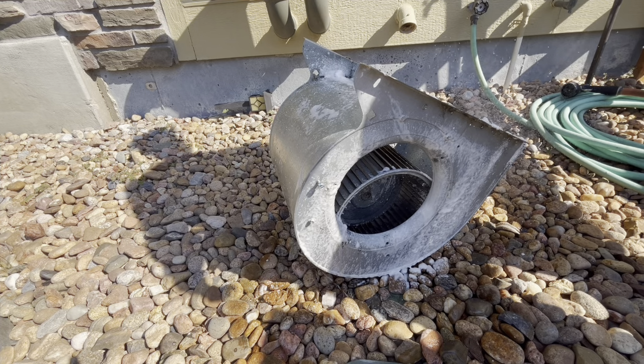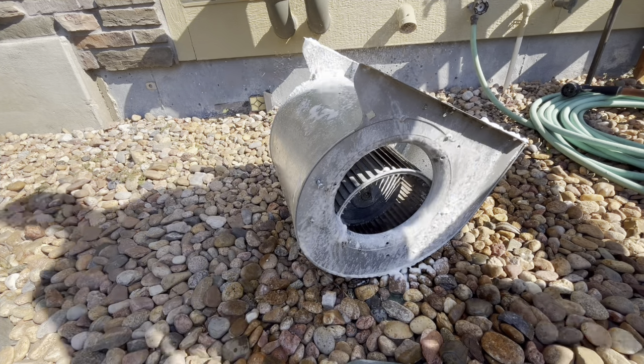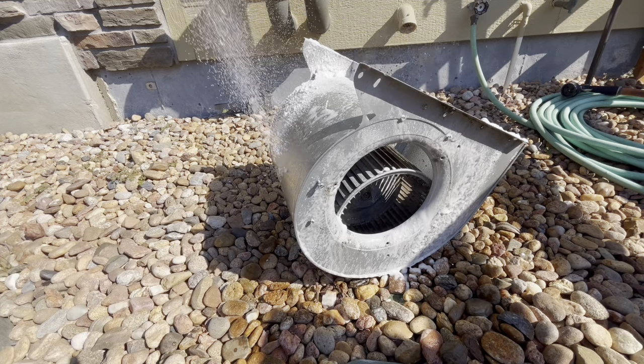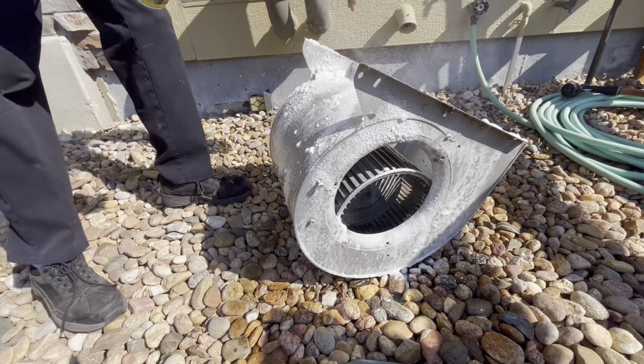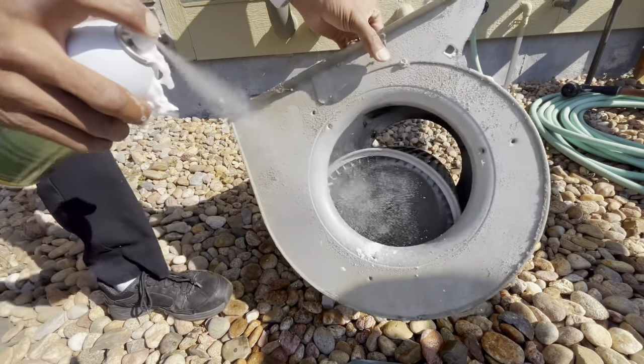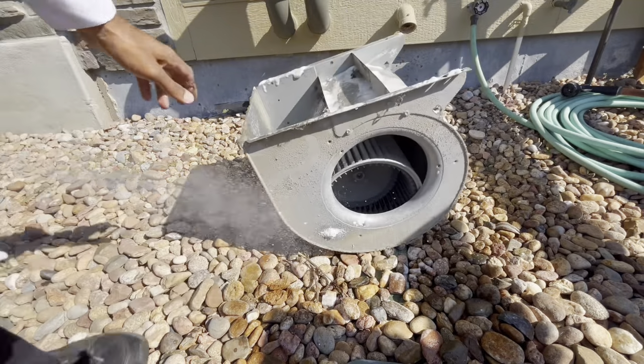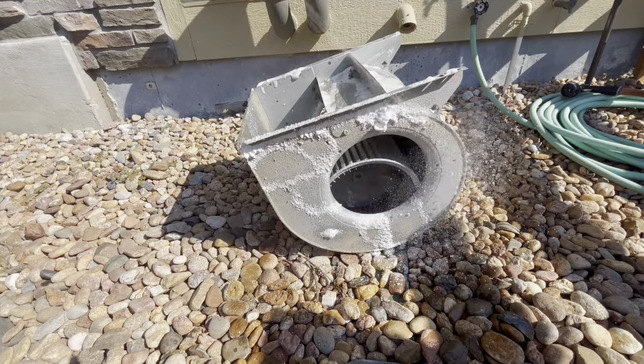So, going through every nook and cranny, going to spray every side of it, and then I'll take my brush and start brushing all the dirt, and we'll rinse it here in a little bit. But we're also checking to make sure that this blower housing is still in good condition, that it's not becoming loose.